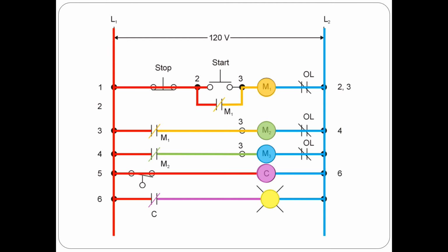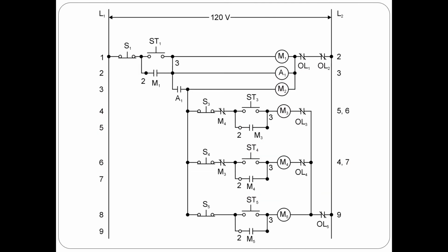high pressure situation. By understanding how schematic diagrams work and understanding the sequence of operation within a diagram, we can use that information to troubleshoot it. We're going to analyze the diagram that we see on the screen now, and then I'm going to give you certain scenarios of what could possibly be wrong with the circuit. I want you to pause the video after I give you the scenario, and you can figure out what is wrong, and then you continue to see if you're correct.